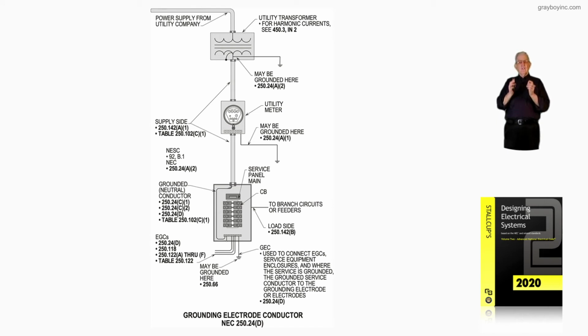And then if you wanted to supplement it, if the utility would let you, you could also ground at the meter base and supplement. Or supplement, running from the grounded bar in the service equipment over to a driven rod. Our utility won't let you get in a meter base and ground. But some utilities will. You have to check that out with the authority having jurisdiction of the state, county, or city, and the utility for what county you're in, because they all have a little bit different rules.